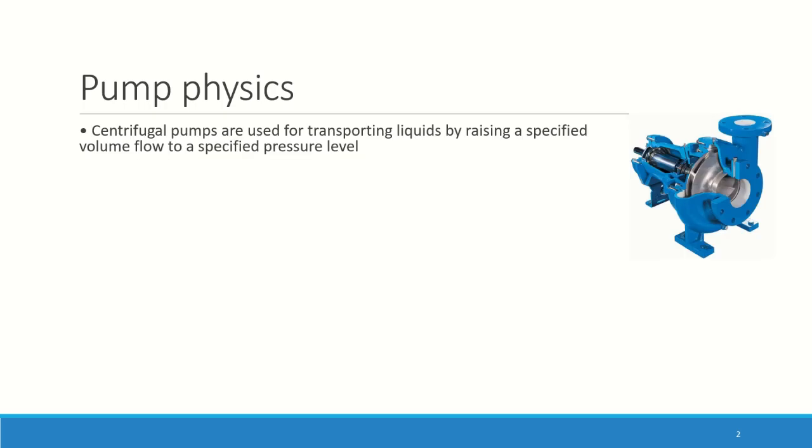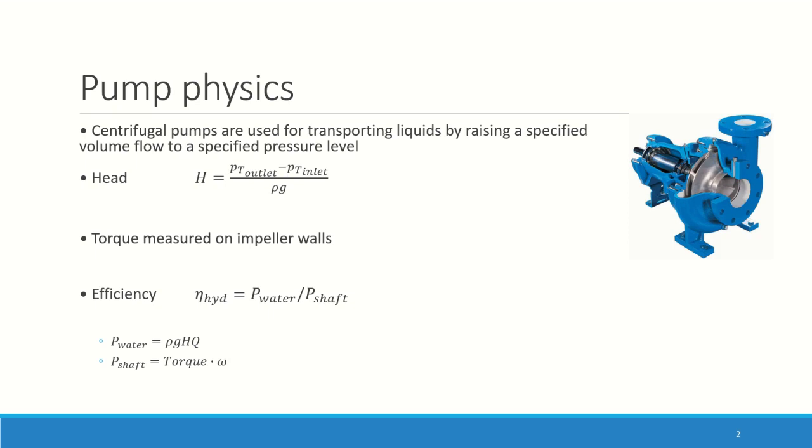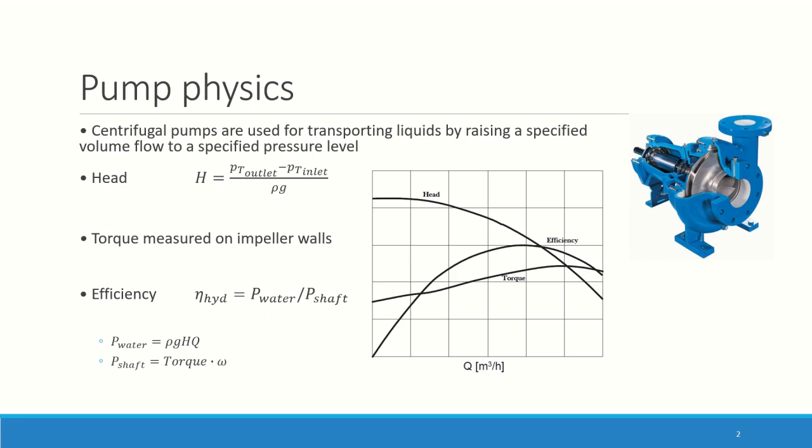The purpose of pumps is to raise the pressure of liquids. How do we measure this pressure? We use the so-called head. So we measure the total pressure on the outlet minus the total pressure at the inlet. The torque we measure on the walls of the impeller, the rotor, and the efficiency or hydraulic efficiency, which is the ratio of the water power divided by the shaft power. We're going to measure them at five flow rates and plot curves.